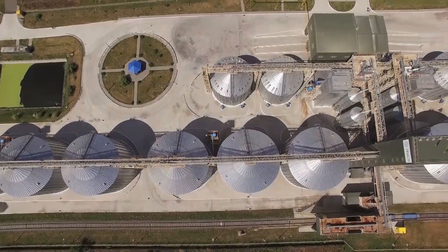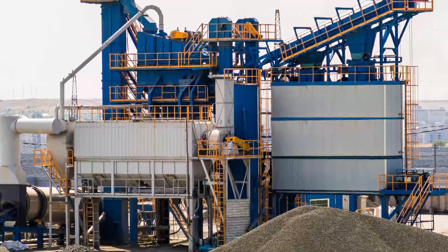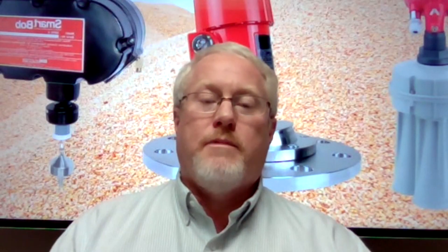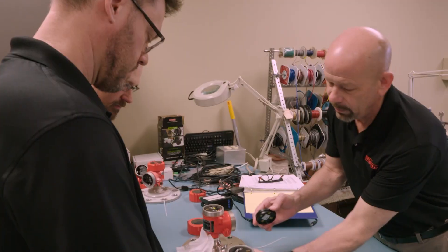Is there anything else you might recommend to plants? We definitely recommend coming to your silos with a belt-and-suspenders approach — having both continuous measurement for inventory management and point level measurement for your high and low measurement points. A lot of people skip the point level measurement because they have continuous measurement and think that covers their concerns, but you really should use continuous level measurement to manage inventory and point level measurement to control your process — turning off and on pumps, conveyors, whatever your process happens to be. For a few hundred extra dollars, you can save yourself a lot of grief from an overflowed bin or plugged conveyor.